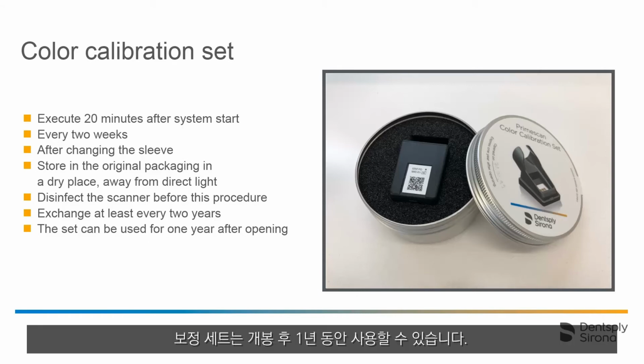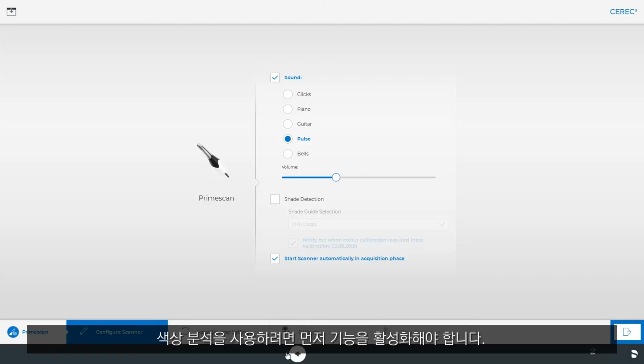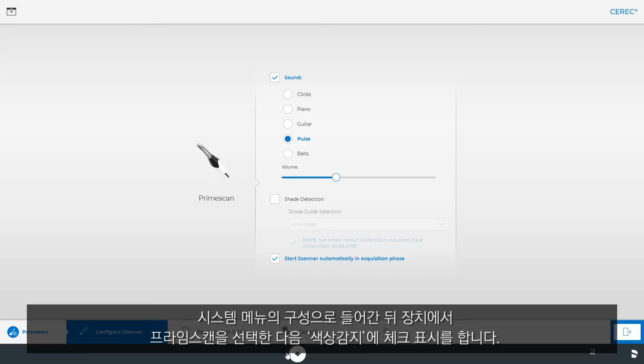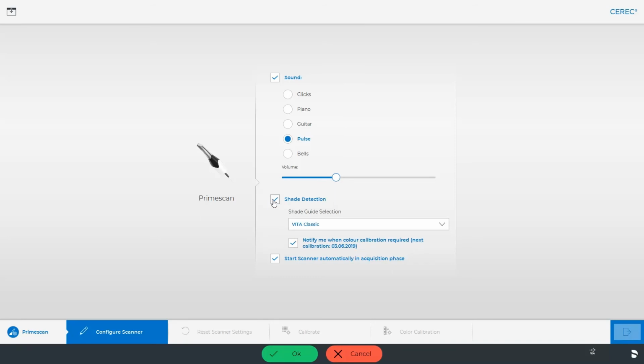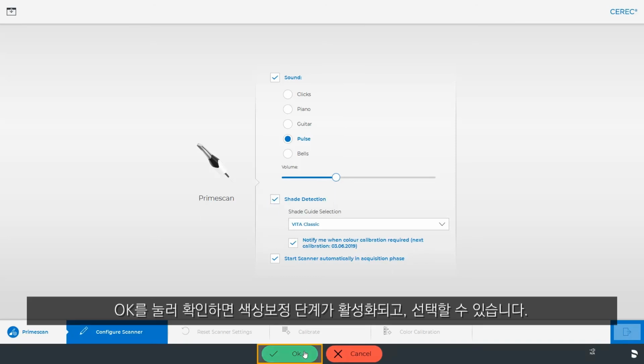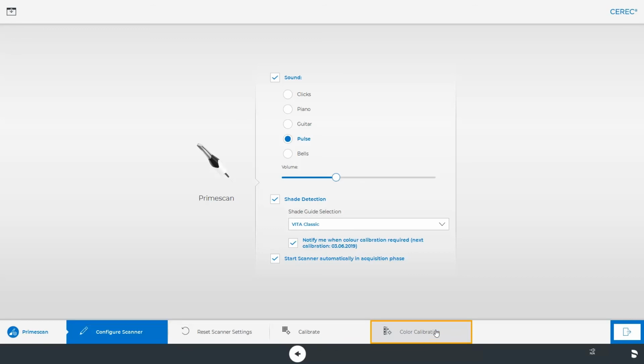After opening the container, the set can be used for 1 year. Use a waterproof pen to write the opening date on the lid of the container after it is opened. To perform a color analysis, we must first activate this function. We go back to the System menu under Configuration, into the sub-menu Devices, select PrimeScan, and then place a check mark at Shade Detection. After we confirm with OK, the step Color Calibration is activated and we can select it.